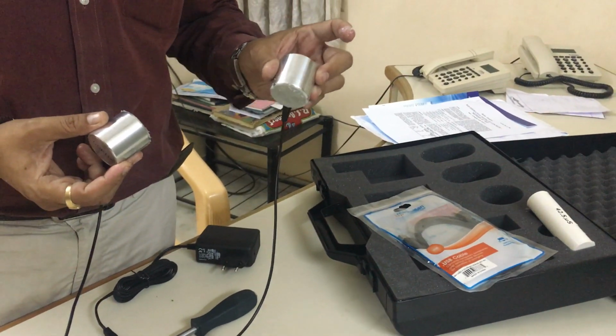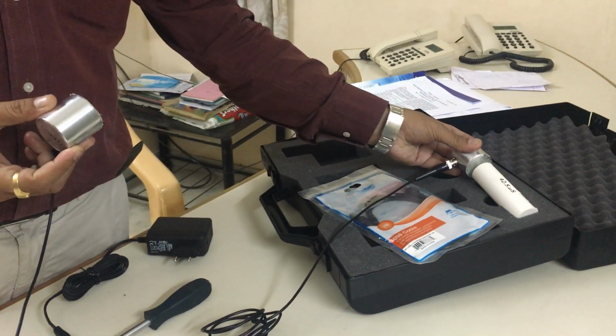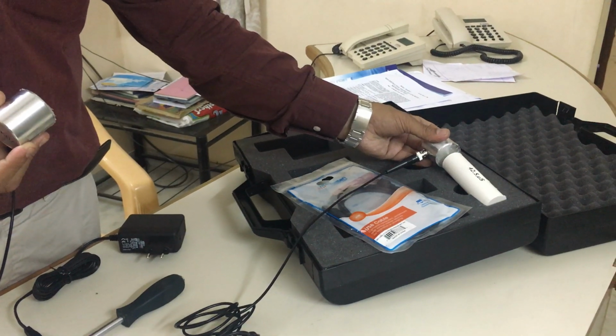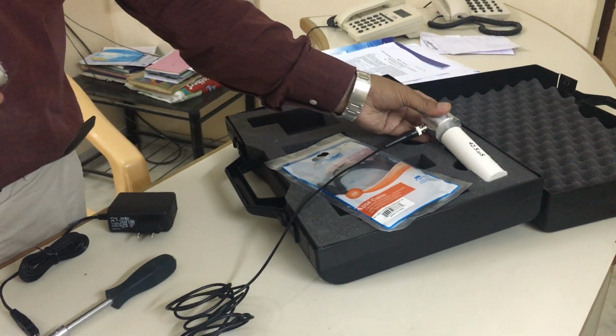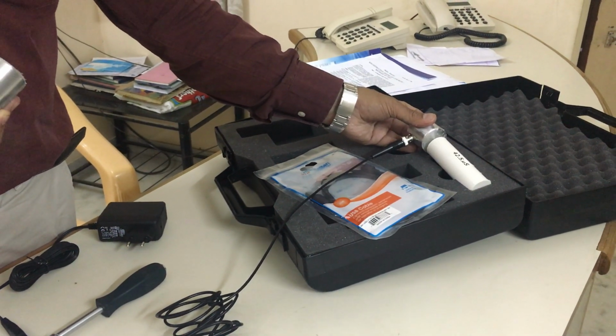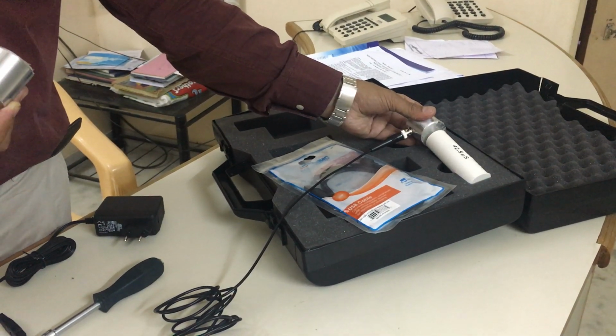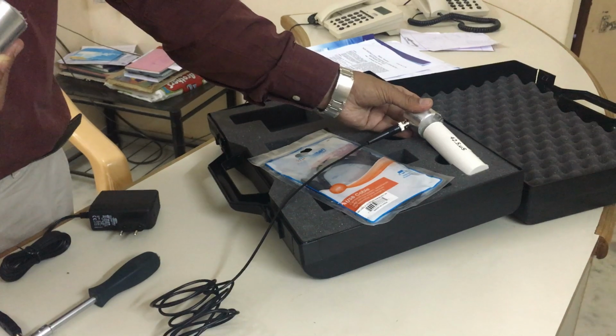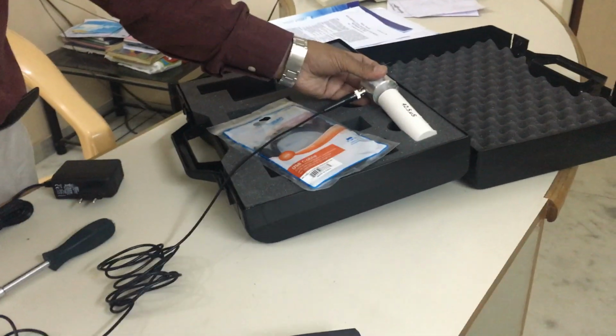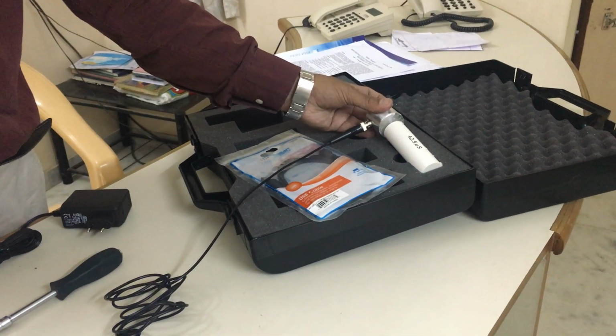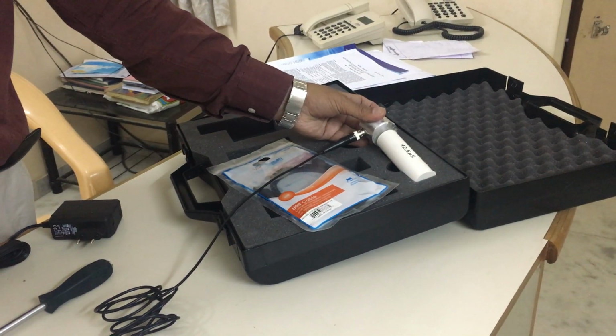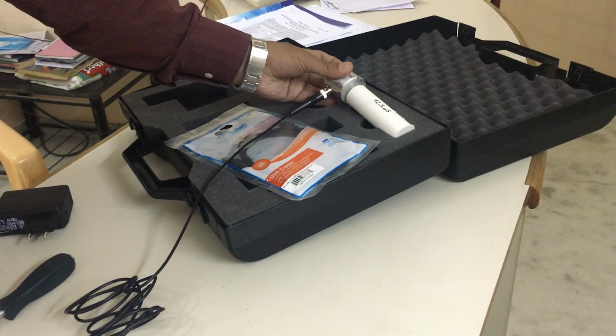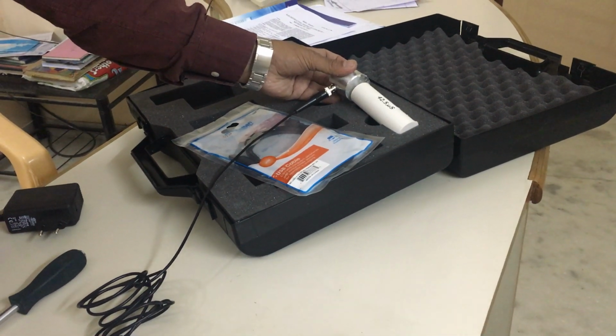Now, why is it required? What does it give you? It gives you the time of flight, the time of travel. There is a transmitter which transmits ultrasonic pulse waves, and when they are transmitted they go into the sample. Depending upon the type of sample or geometry, complex waves are created. It could be shear waves, longitudinal or compressive waves, or surface waves. Now what does this ultrasonic pulse measure? It measures the compression, longitudinal waves, which are independent of the geometry of your sample and depend more on the elastic properties of the sample you are testing.